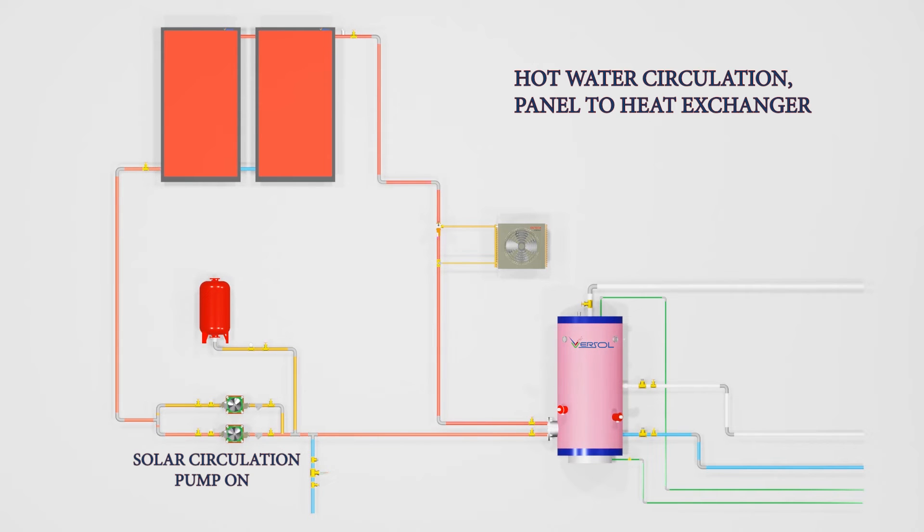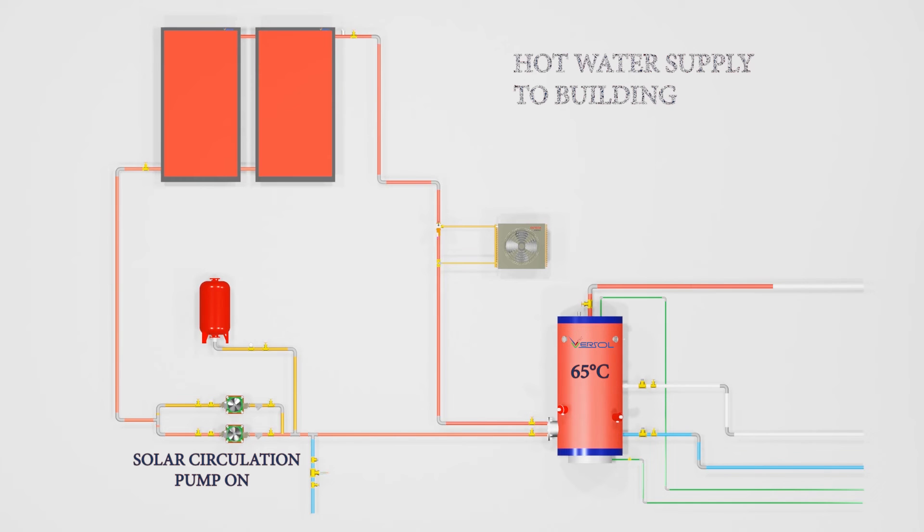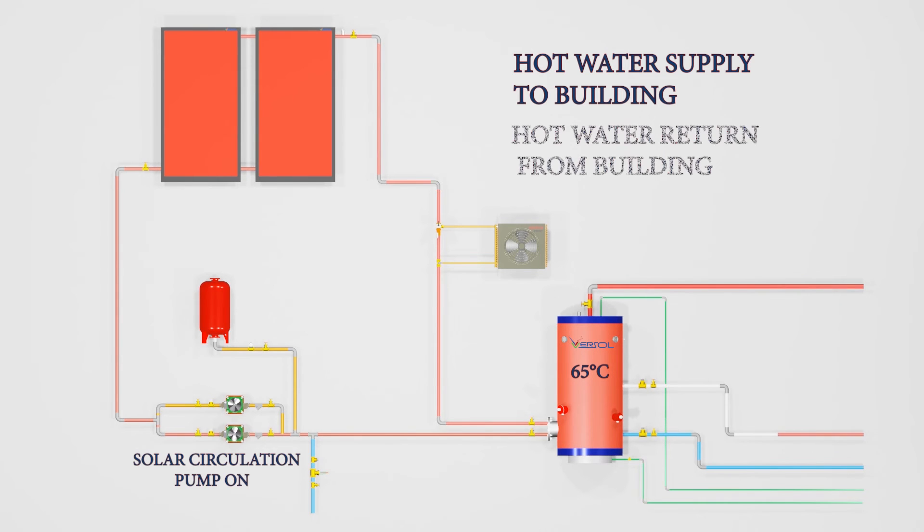In continuous operation, the storage tank temperature increases. Once the system reaches the set temperature, solar circulation pump will be turned off to avoid overheating. Now you can start the hot water circulation pump and enjoy your hot shower. Hot water from the building returns to storage calorifier and the entire process continues.